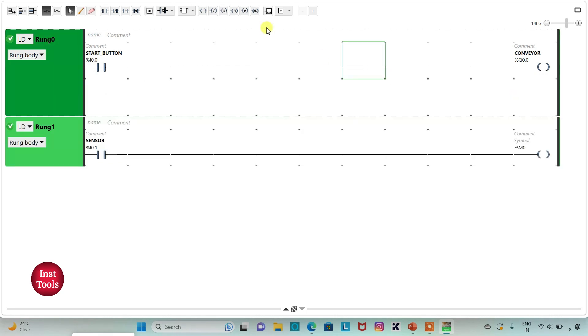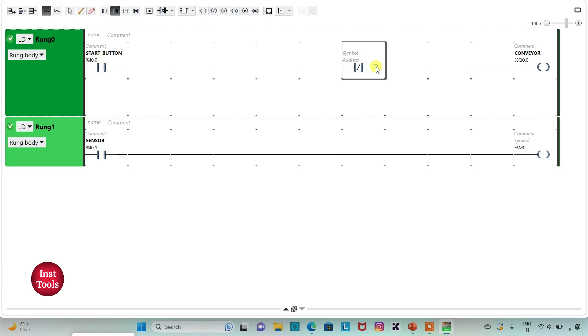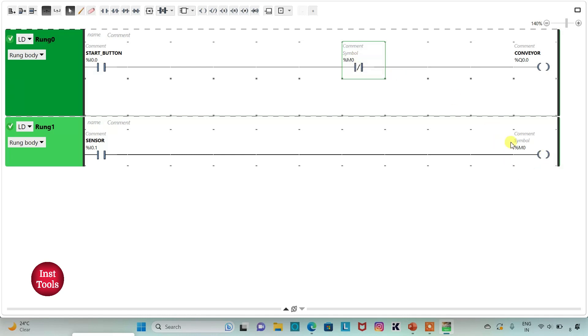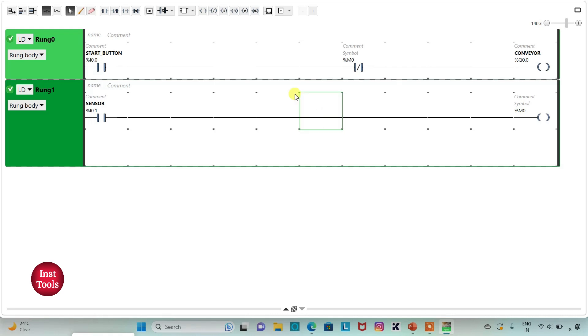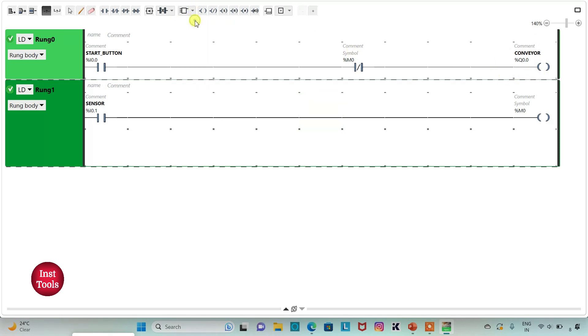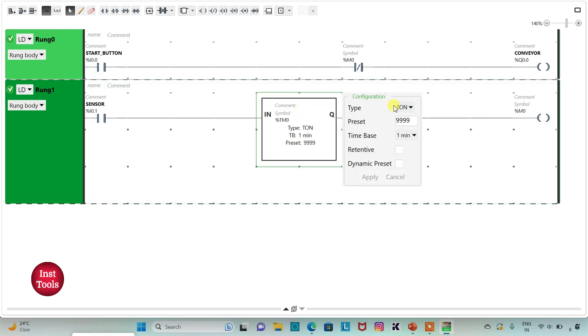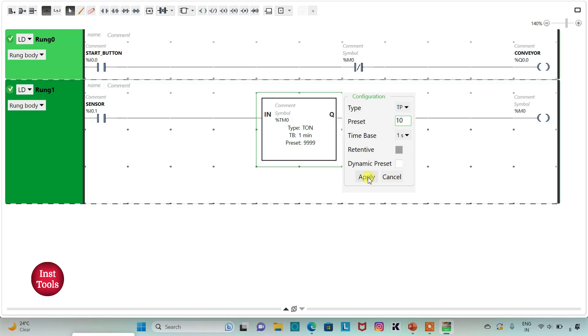So here I will insert a normally closed contact that will help us to stop the conveyor — M0. So the memory bit should remain on for 10 seconds. So I will insert a timer here, and that should be TP. I will change the time base to 1 second and preset value to 10, and then apply.